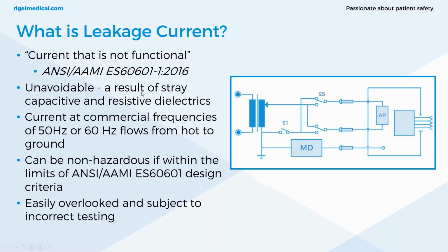So it's unavoidable. It's a result of stray capacitive and resistive dielectrics. Current at commercial frequencies flows from live to earth, or hot to ground. Again, that's terminology. I said live to earth, but hot to ground is what's used within the United States. All mains powered equipment is designed to ensure safe levels of leakage current. Any powered device, you cannot eliminate leakage completely. What you're doing is trying to limit it within a safe limit.